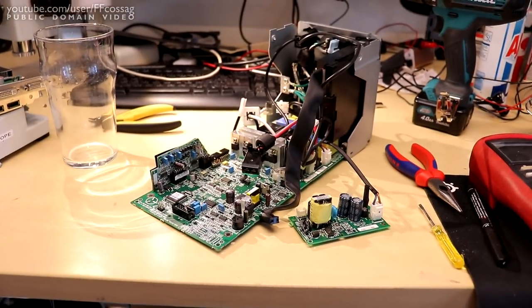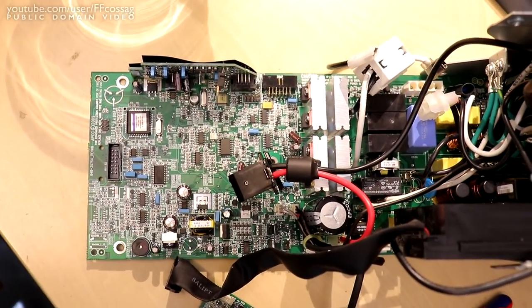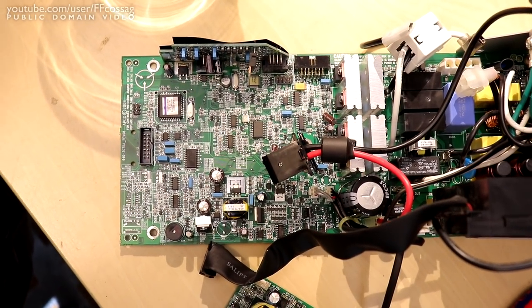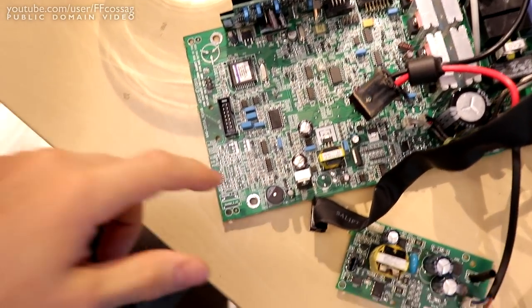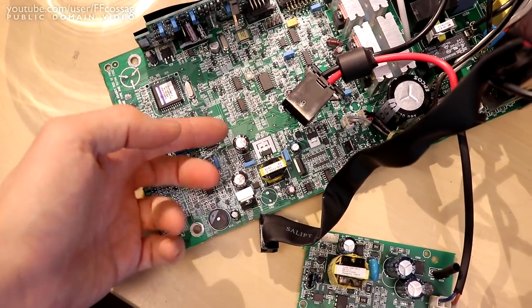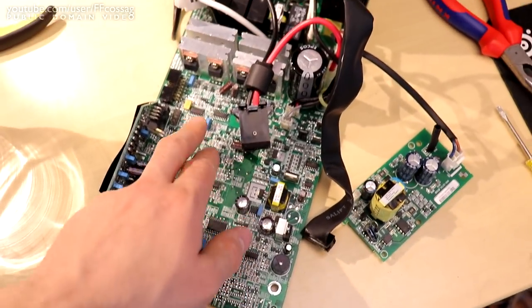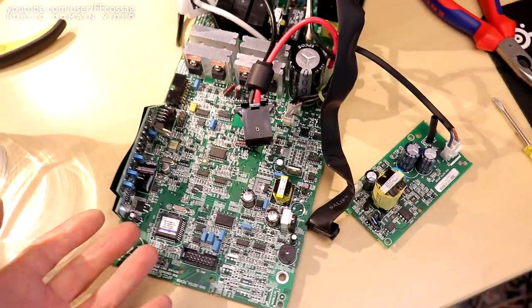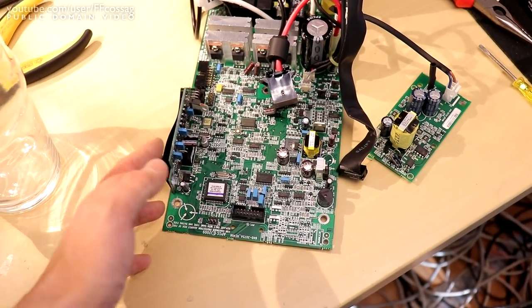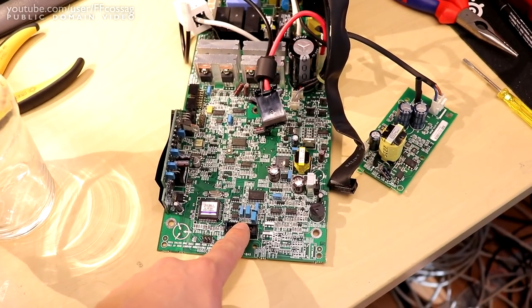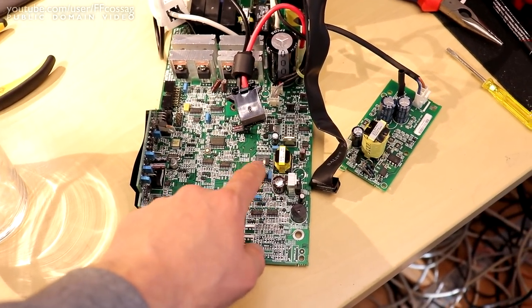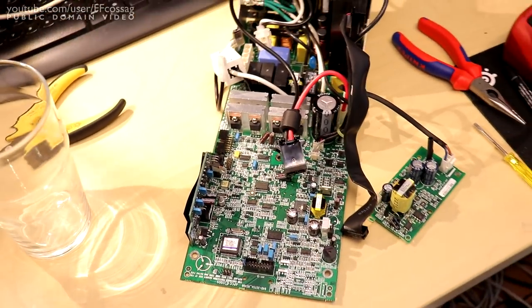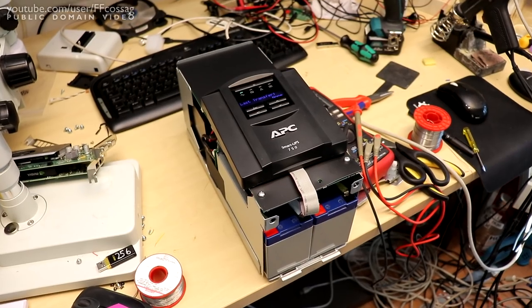Just wanted to give you guys a quick look inside one of these slightly more modern APC units. They do seem decent, but sadly these caps are actually causing failures of these, as opposed to the old ones where these 22 microfarad caps would just go bad and slosh around and wouldn't really hurt performance. But these seem to actually get reliability issues when they get old. Real shame, but probably decent otherwise.